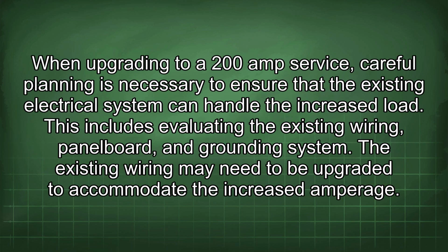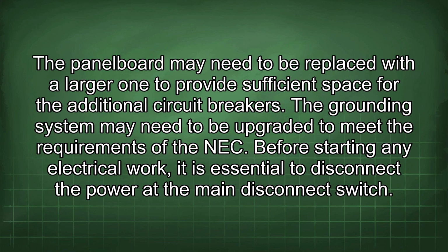When upgrading to a 200 amp service, careful planning is necessary to ensure that the existing electrical system can handle the increased load. This includes evaluating the existing wiring, panel board, and grounding system. The existing wiring may need to be upgraded to accommodate the increased amperage. The panel board may need to be replaced with a larger one to provide sufficient space for the additional circuit breakers. The grounding system may need to be upgraded to meet the requirements of the NEC.